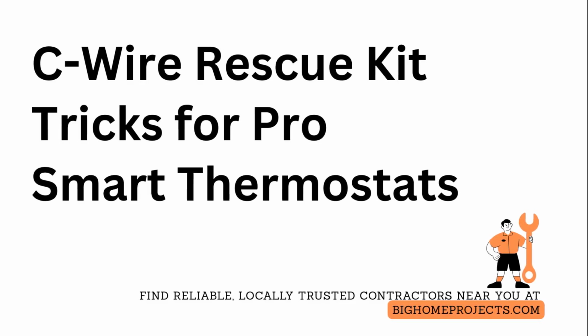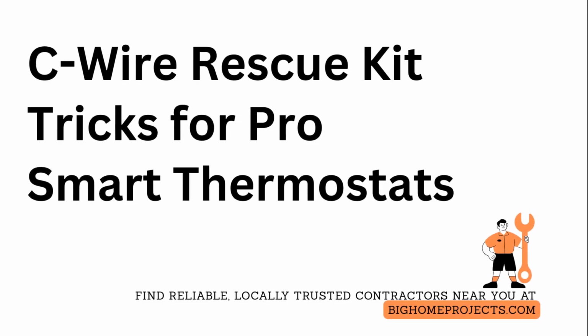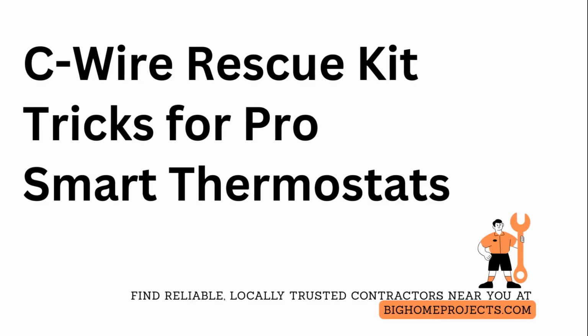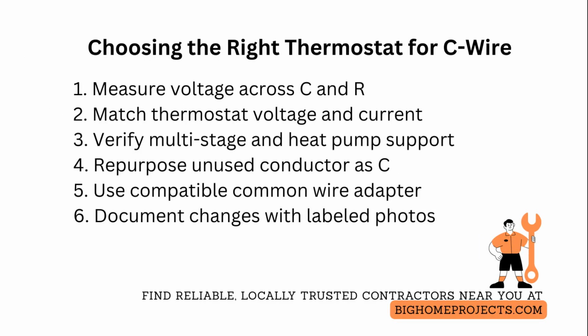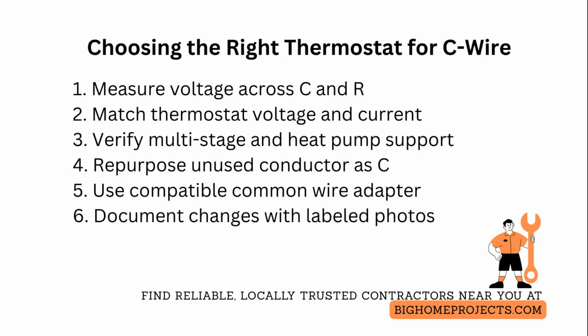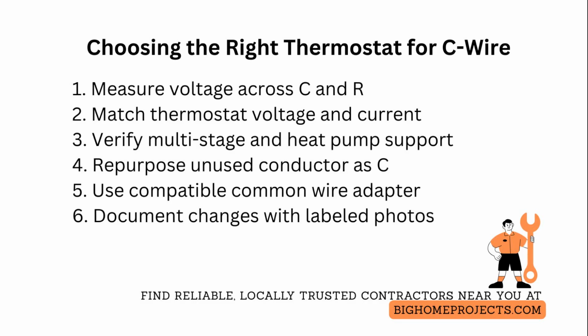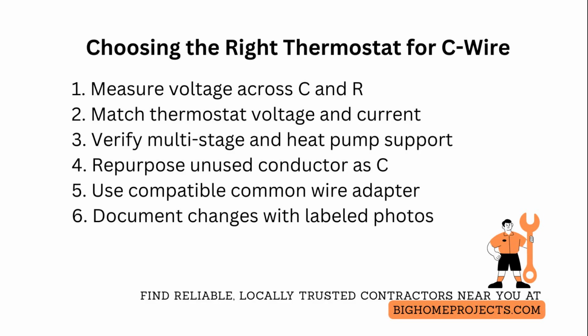Choose a thermostat that supports a common wire so you won't be stuck with limited features or constant battery swaps. If your heating, ventilation, and air conditioning control board has a common wire provision, confirm voltage type and transformer amperage first. Many installers miss that a 24-volt alternating current transformer under the furnace may supply different current capacity than the thermostat spec requires, so measure the idle voltage across the C and R terminals with a multimeter before buying.